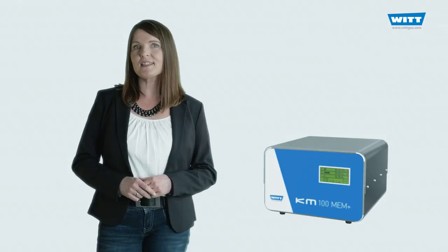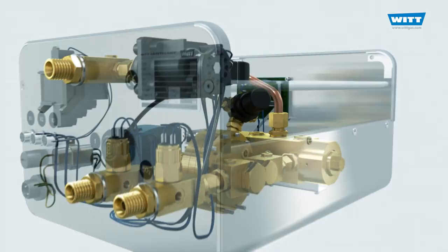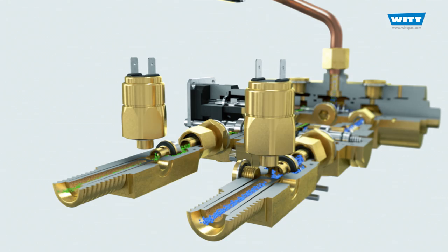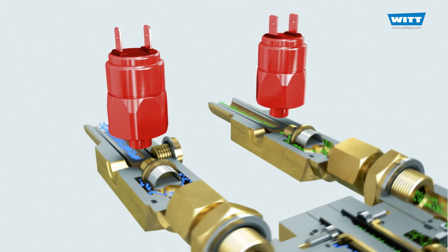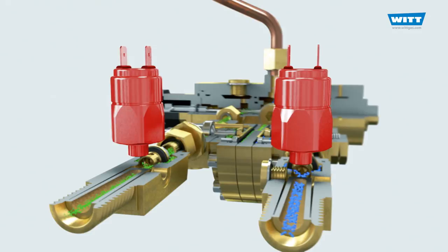The KM100 MEM+ comes with inbuilt simplicity and high quality, just like the way it operates. The inlet gas passes by the inlet pressure monitor. Too low or too high inlet pressures impair the correct functioning of the mixer. Pressure transmitters continuously monitor the inlet pressures and trigger an alarm if the set limits are exceeded.